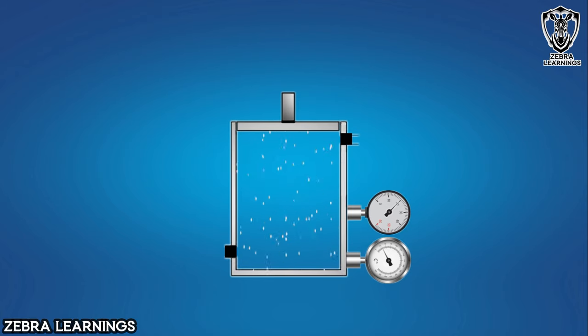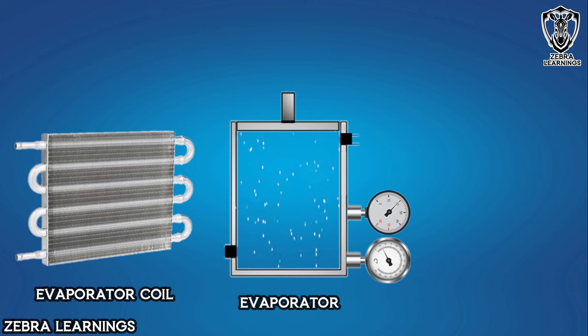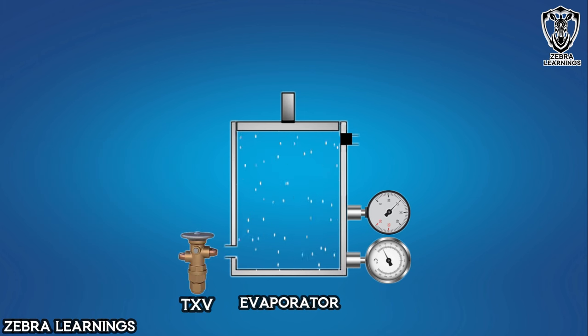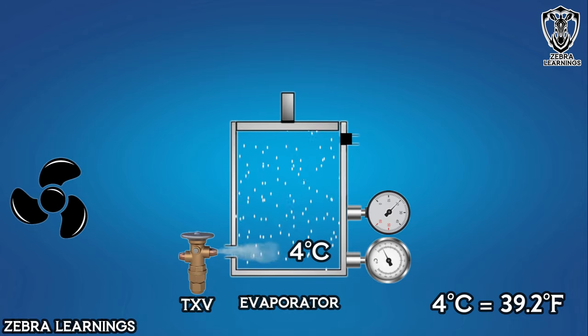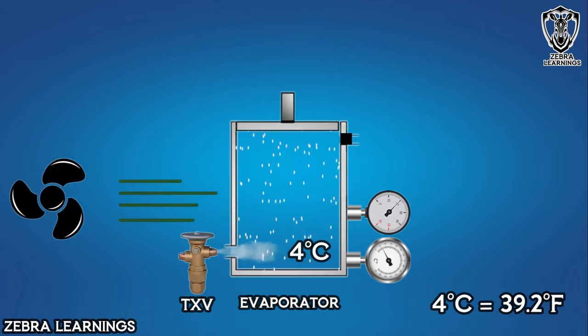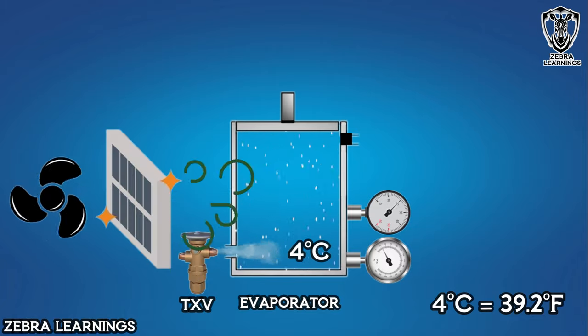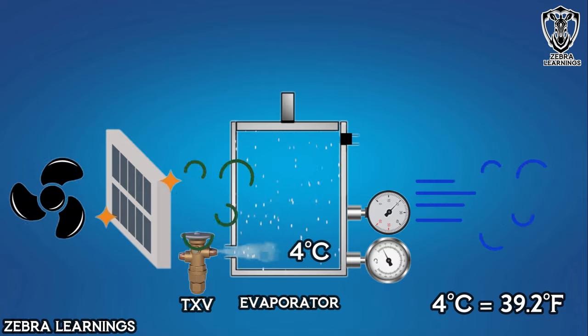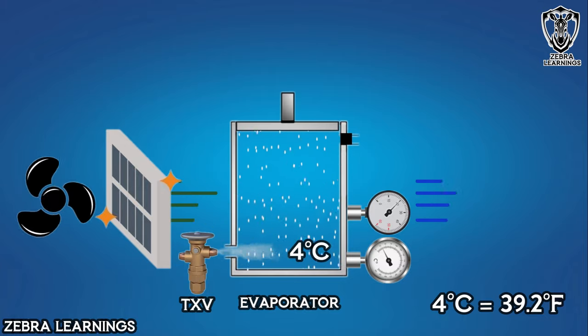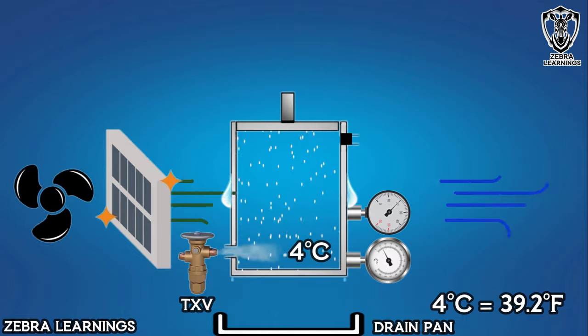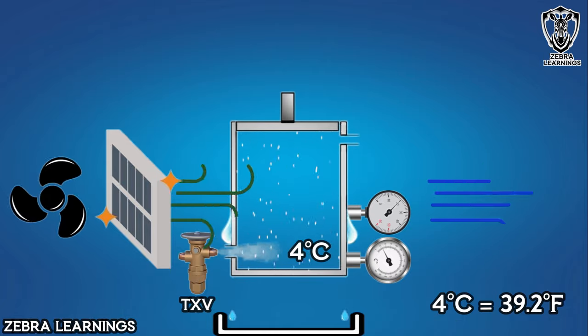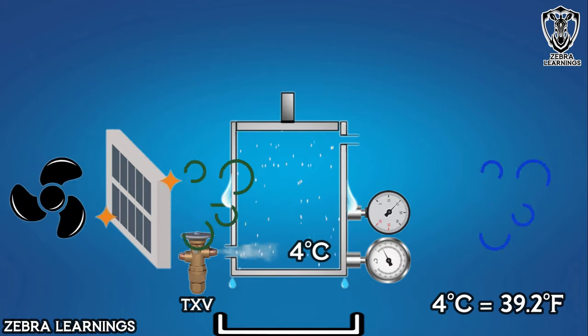Now, this box can be taken as the evaporator. Refrigerant inside it comes from the expansion valve at a certain pressure. When entering the evaporator, the refrigerant temperature is up to 4 degrees Celsius. Behind the evaporator coil, there is a blower motor. It keeps blowing air over the evaporator. There is a filter to filter this air. When this air hits the evaporator coil at a temperature of 4 degrees Celsius, we get well-cooled air. Condensation occurs in the evaporator when the hot air coming from the blower falls on the evaporator. All this condensation water will go out through the drain pipe.